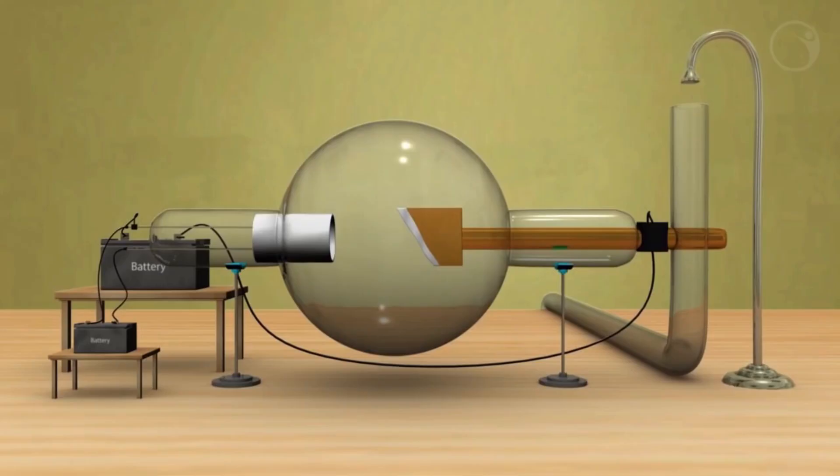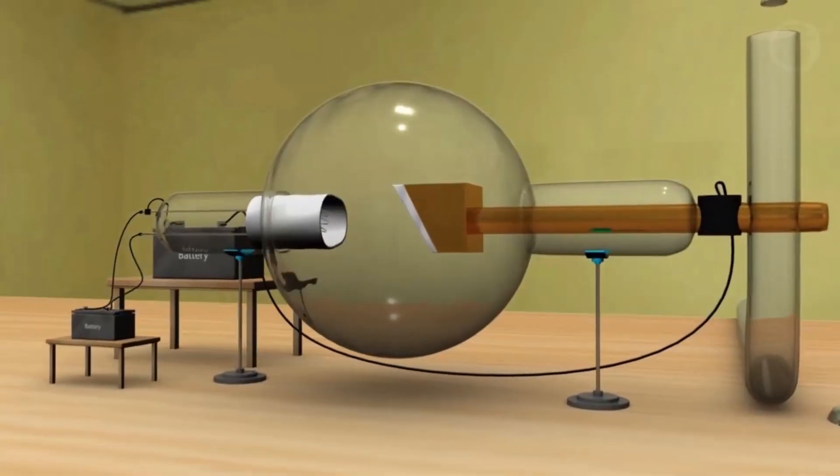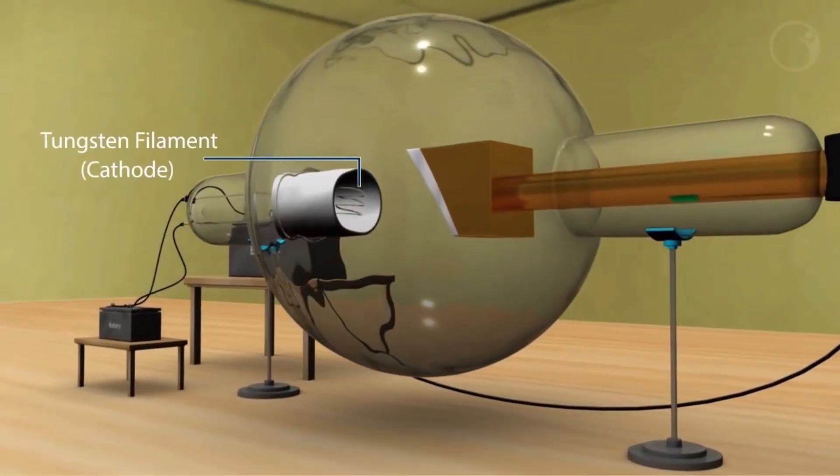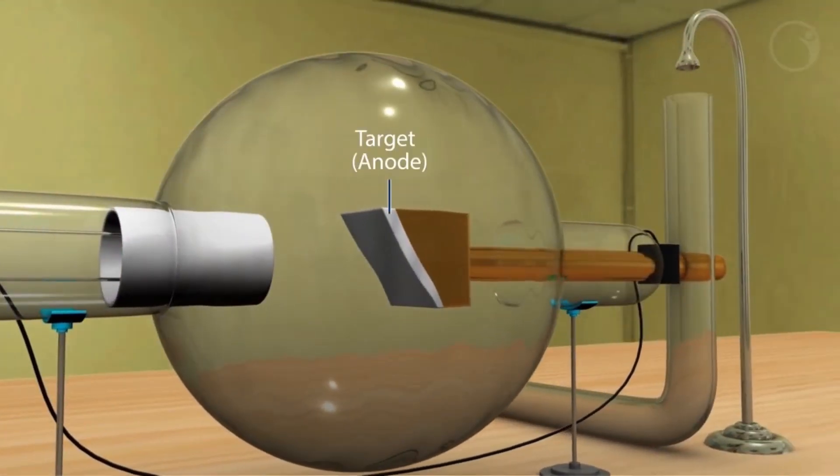Let's end this video with x-ray generators. Three types of x-ray generators have been and continue to be sold for cardiac cath labs: three-phase mA-switched, three-phase kVp-switched, and high-frequency inverter units.